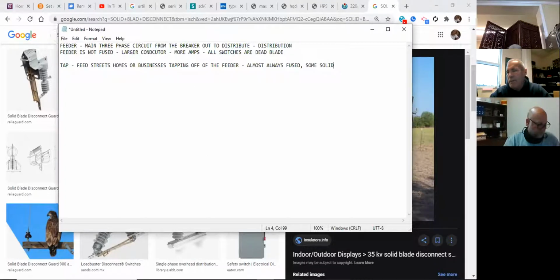If we have, say, a squirrel get on a fused tap that's going down a street and feeding one house, we don't want it to be solid or wired directly to the feeder. We want a fuse in there, because if we have a fault down there, it's going to isolate itself with a fuse. If it's solid, it's going to take out the entire feeder. So for one customer on a solid tap, we want that isolated, just one, not taking out thousands because we have a solid tap. Does that make sense? We want fused isolation.